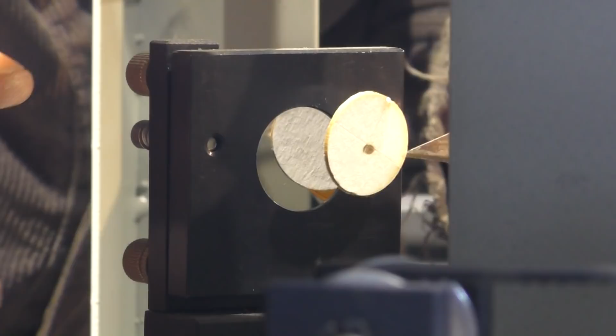I should be able to now very easily just pick this out of here, and if we're lucky, we take a look carefully at that mirror, we will have done no damage to the mirror at all. But if you can see any sort of spot or anything, little teeny weeny haze mark on that mirror, just go and clean it with a little bit of isopropyl alcohol. You need to be sure that it's clean before you move on. Now we're at the back of the machine, as you can see, because here's the laser tube.